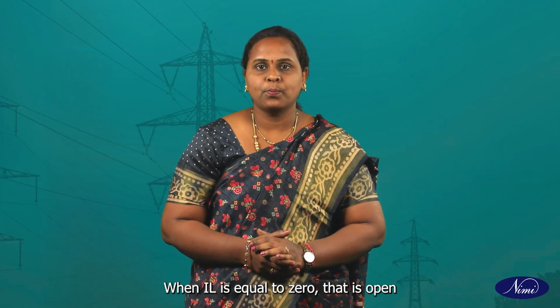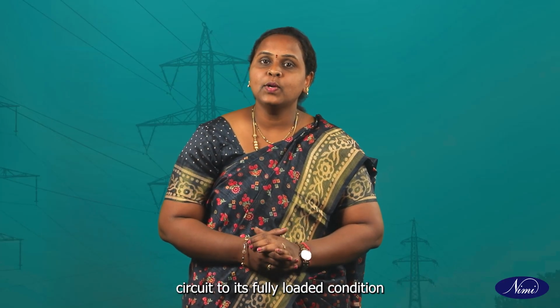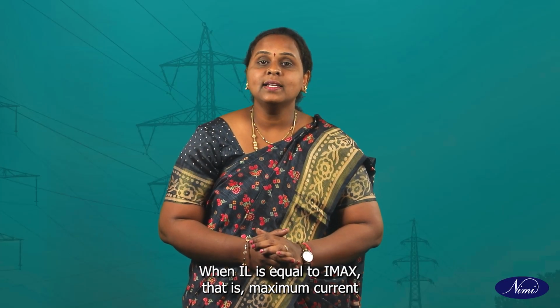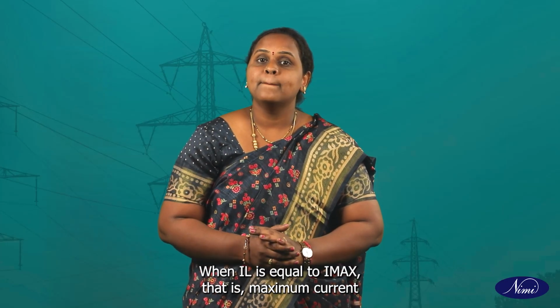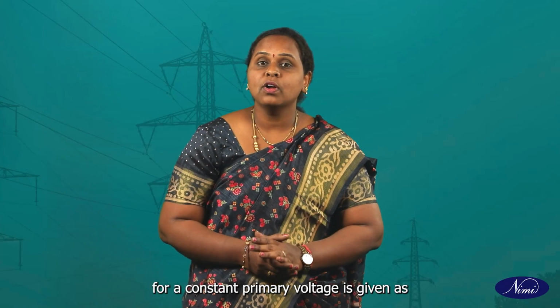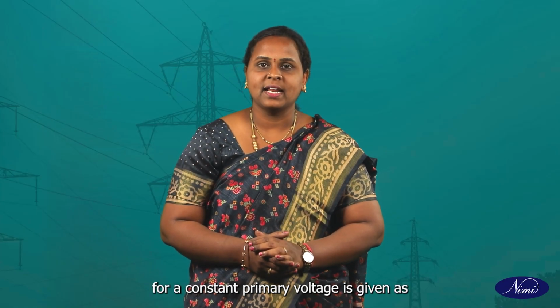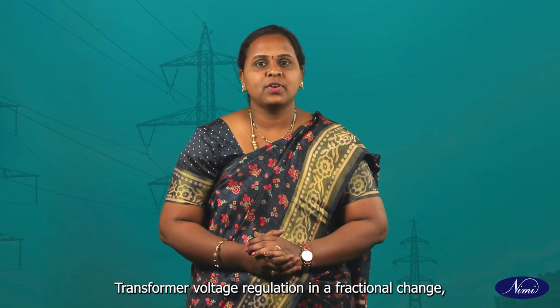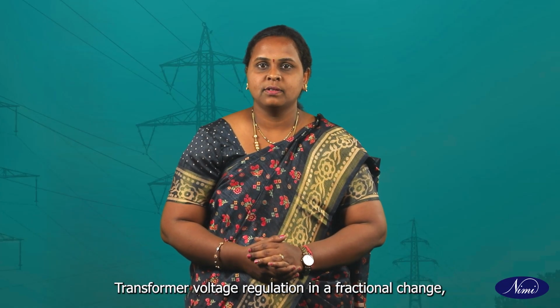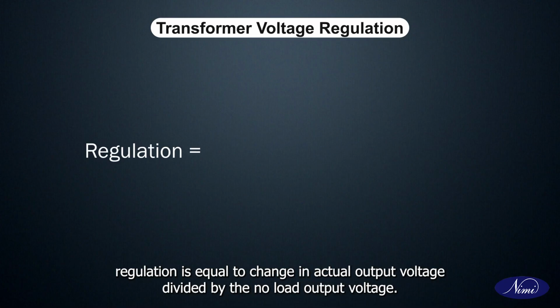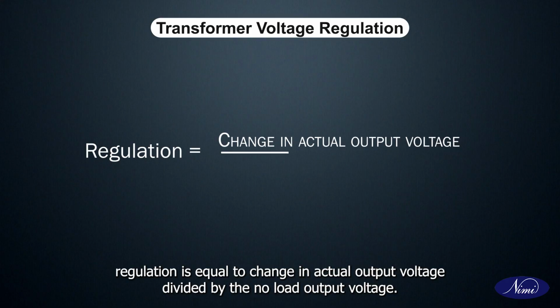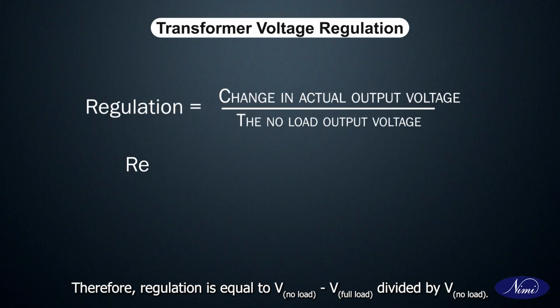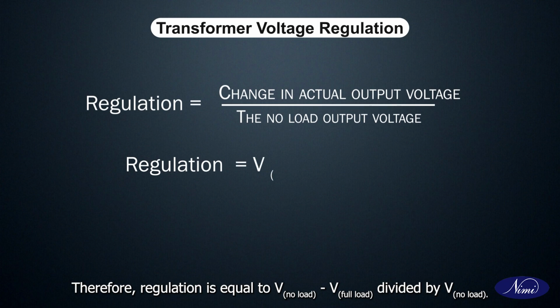A transformer voltage regulation changes between its secondary terminal voltage from a no load condition, when IL is equal to 0, that is open circuit, to its fully loaded condition, when IL is equal to Imax, that is maximum current, for a constant primary voltage. It is given as transformer voltage regulation in a fractional change. Regulation is equal to the change in actual output voltage divided by the no load output voltage. Therefore, regulation is equal to V no load minus V full load divided by V no load.